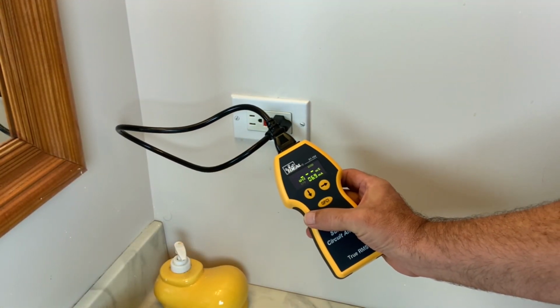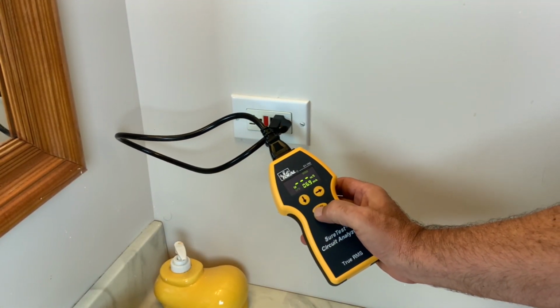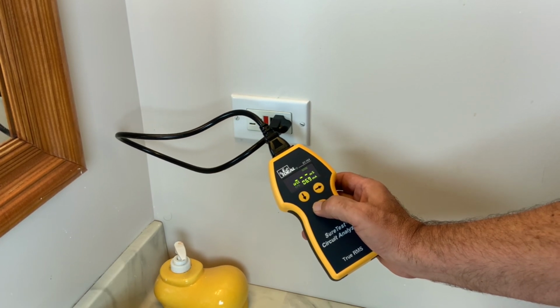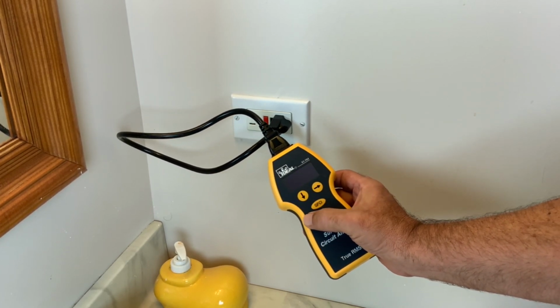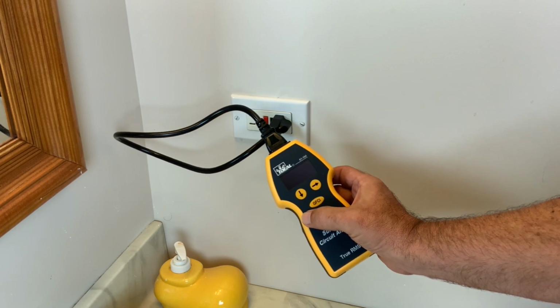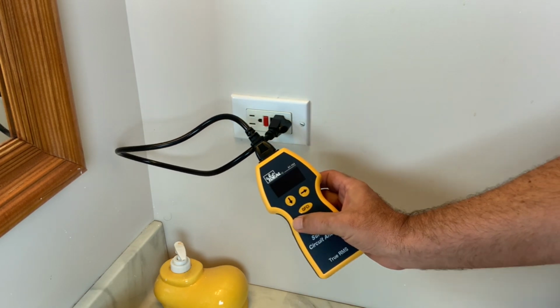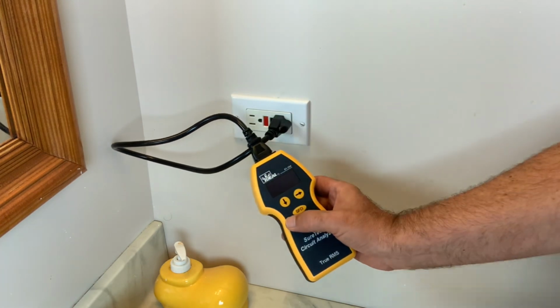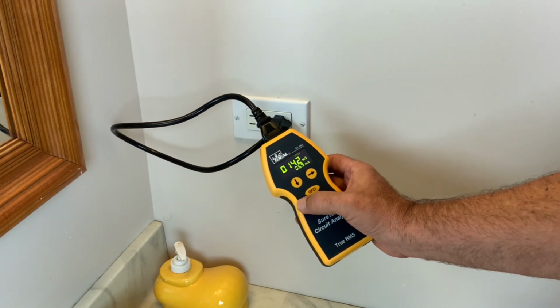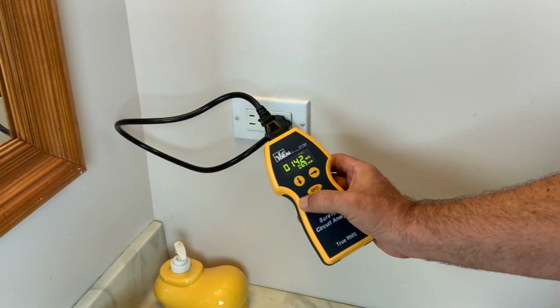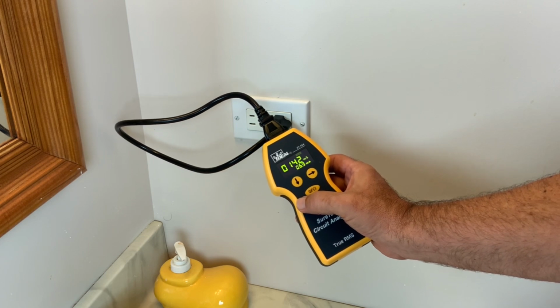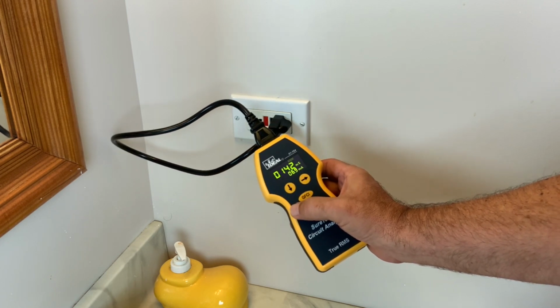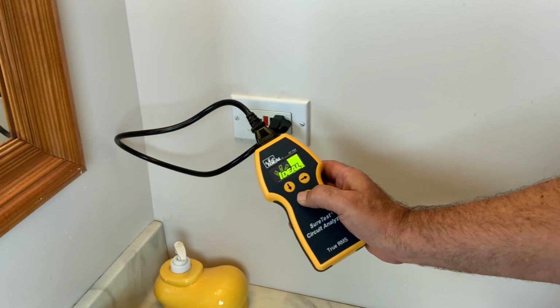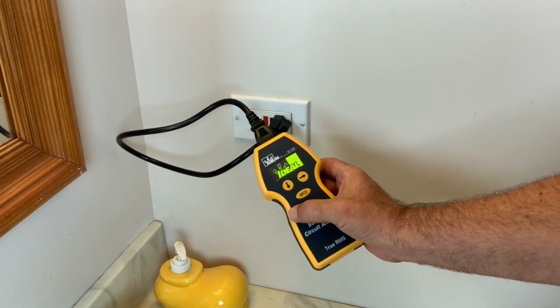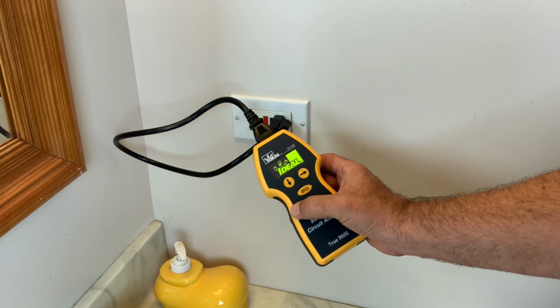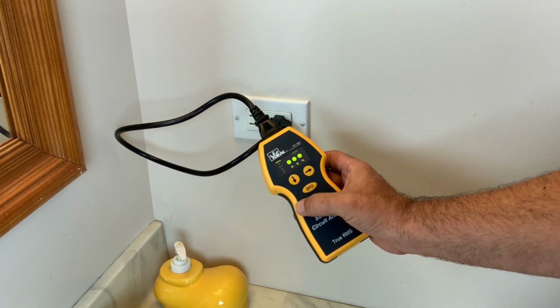So to perform the GFCI test, simply hit the GFCI button after you're plugged in and on this screen. And once you test the outlet, the tester will lose power because you've now tripped that GFCI outlet. So once you reset the outlet, it will show you the amount of time it took for that outlet to trip, 142 milliseconds at 6.9 milliamps. So it won't do any of the other testing until after you hit the GFCI again. Now the tester will power back up and do the measurements on this outlet the way that it normally does.